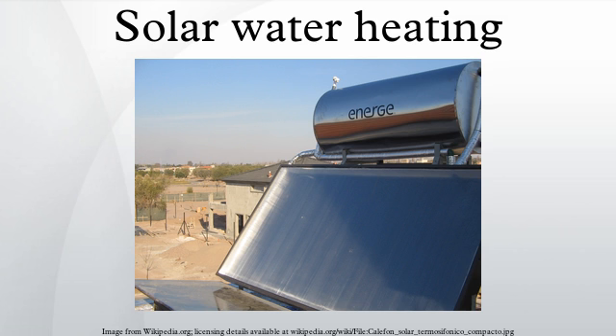Types of solar water heating systems: direct and indirect systems. Direct or open-loop systems circulate potable water through the collectors. They are relatively cheap but can have the following drawbacks: they offer little or no overheat protection unless they have a heat export pump. They offer little or no freeze protection, unless the collectors are freeze-tolerant. Collectors accumulate scale in hard water areas, unless an ion exchange softener is used.